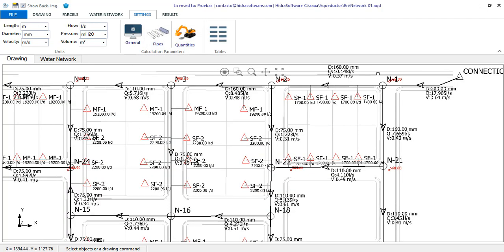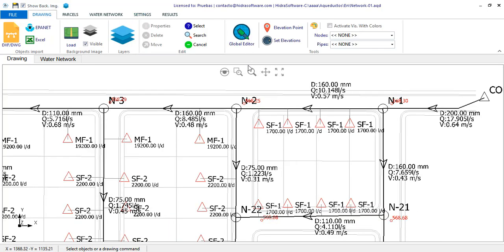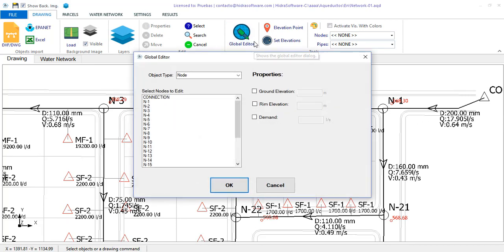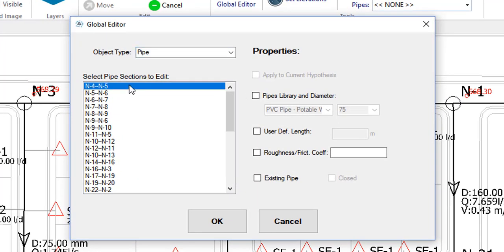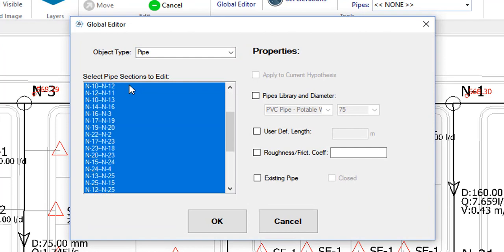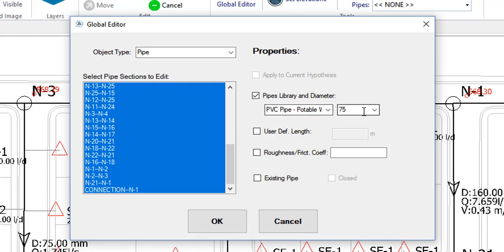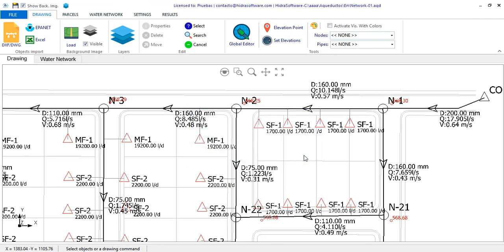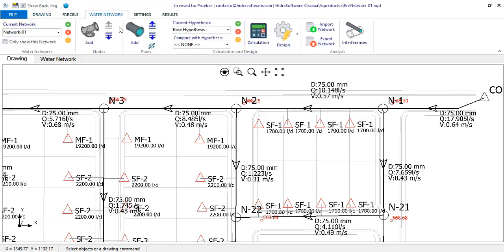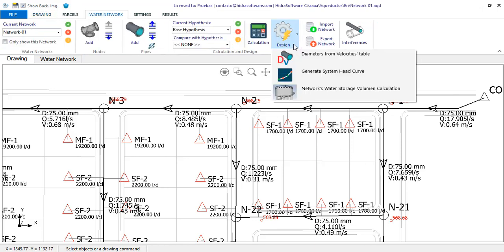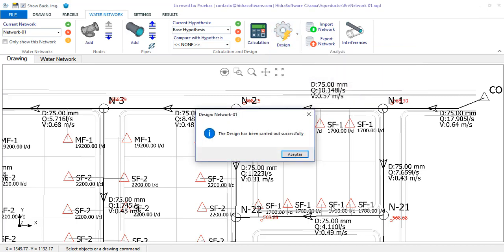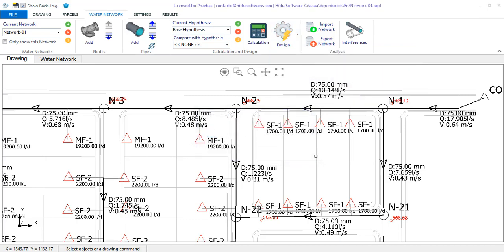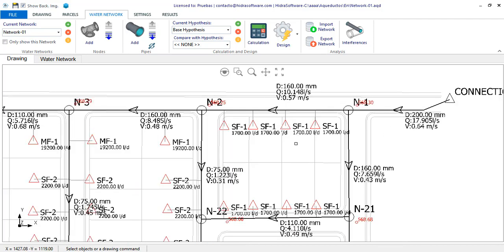But before this, I will use the global editor to set all the diameters at the minimum, so I guarantee that it starts searching for diameters from the smallest possible in each pipe section. Here I can select all the sections by clicking the control keys plus the shift and down arrow from the keyboard. Now, I redo the calculation and design. The diameters change, as in the case in which we use the table of velocities.